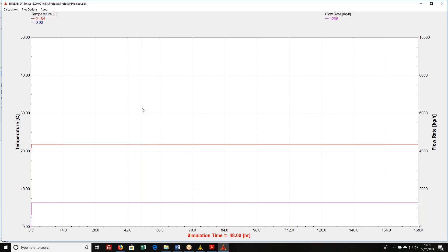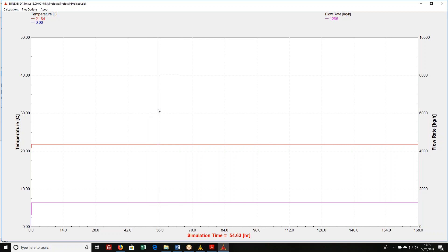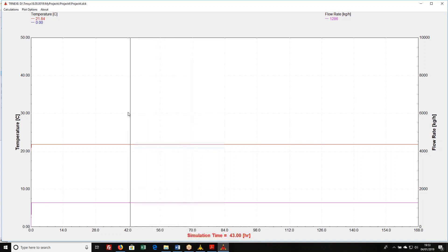It went in at 20 degrees C. It's coming out at 21.84. So however I set this fan up, it's picking up a fair amount of heat as it flows through there. And I can see that the flow rate is 1,286 kilograms per hour.